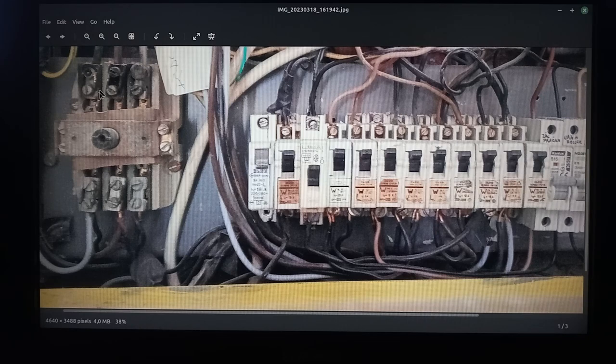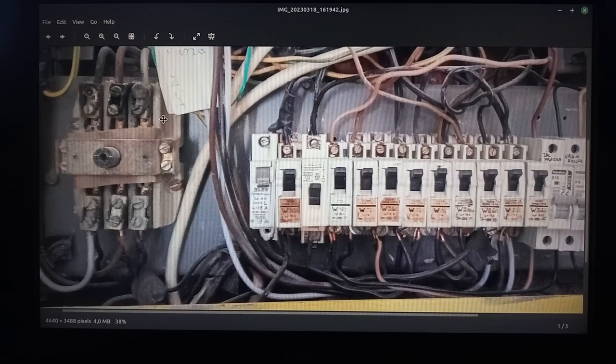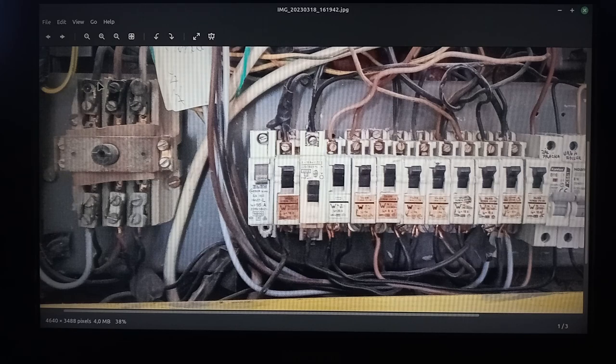This is the main switch and I'm not sure what kind of power it could carry, but this is the incoming cable — 10mm² wires each, so their top limit is about 50 amps legally. They could carry more but legally it's 50 amps, and you could push it up to 63 amps reasonably safely, but normatively it's 50 amps. You can see something happened up here — that brass or bronze color is actual brass because somebody had a screwdriver slip. The culprit admitted he was doing all of the electricity in the house himself, so what you see here is really just the tip of the iceberg.